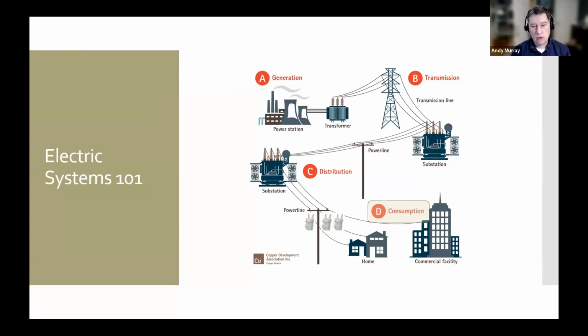Another term that might come up during these discussions is relaying. It's a general term we use for the protection of equipment. The best analogy is the circuit breakers at our house. Your circuit breaker has both the mechanical interrupting, so it opens the circuit when there's a problem, as well as the smarts, if you will. I understand a circuit breaker is about as unsmart a device as you could get, but it has the ability to sense trouble and open.